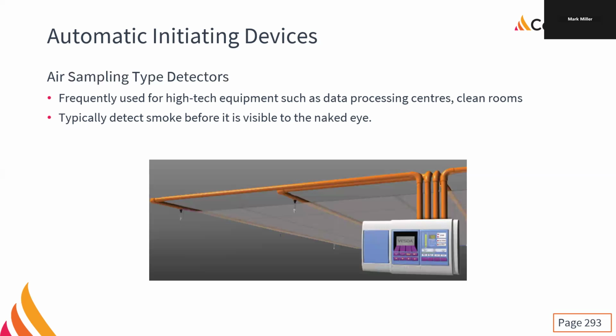The other thing we can do is we can set different thresholds, right? So there's a certain parts per million that is determined to be fire, but we can set other signals at lower thresholds. So, you know, let's say if 10 parts per million is deemed to be fire, maybe at 3 parts per million, we send a signal through the building management system to say, yeah, someone's got to come and have a look, right? Something like that. We can do all sorts of fun things with this.